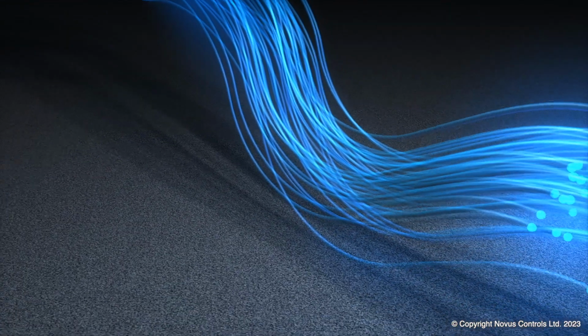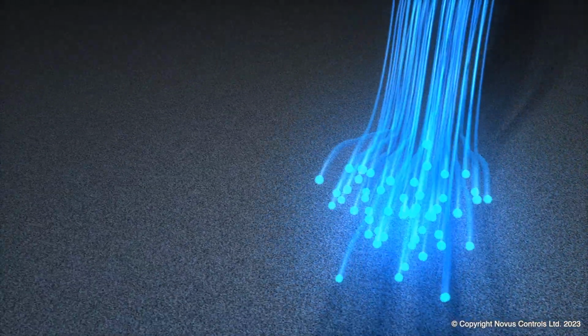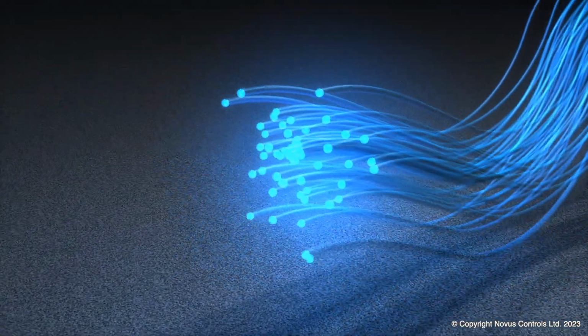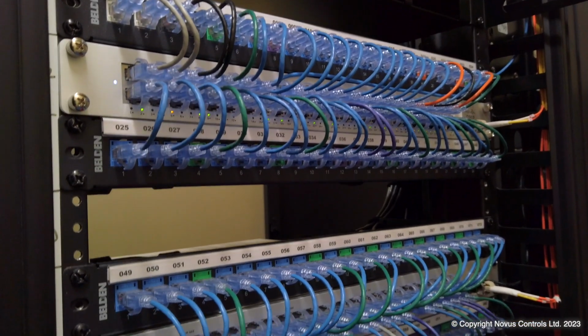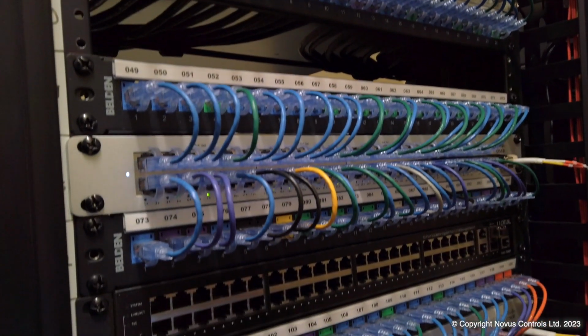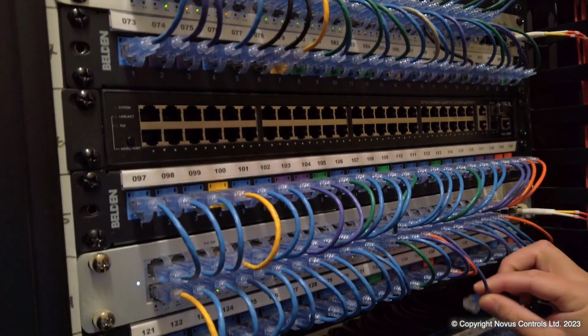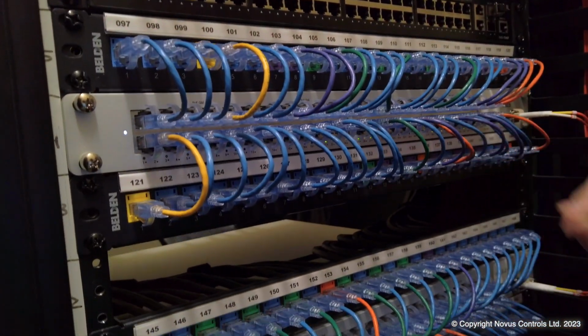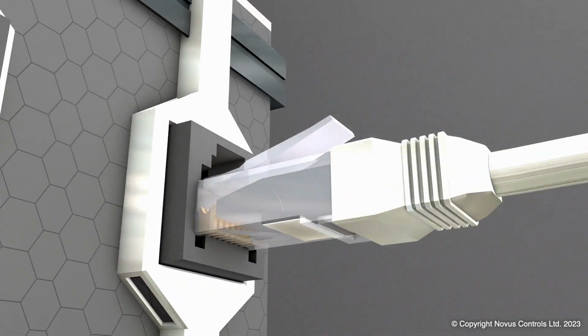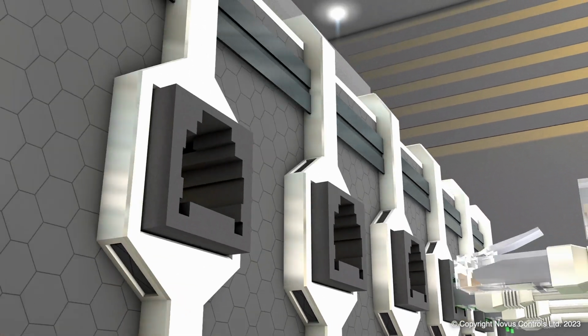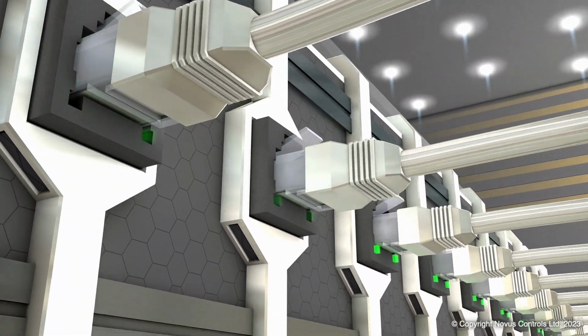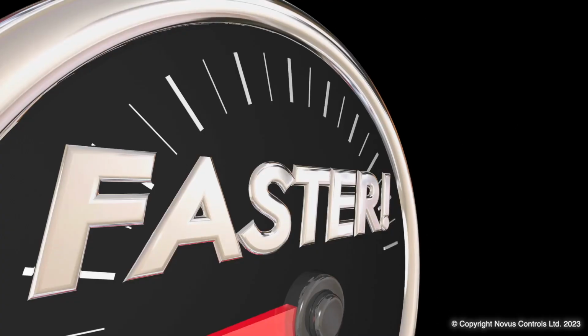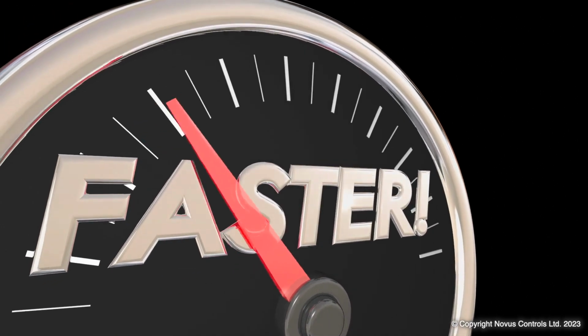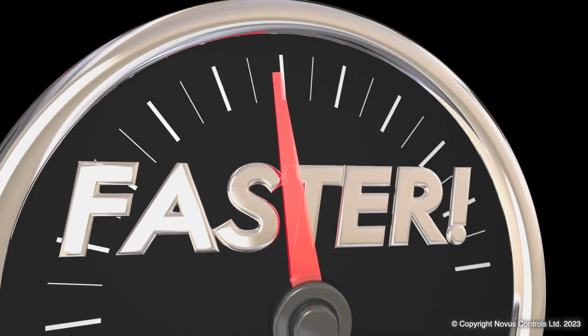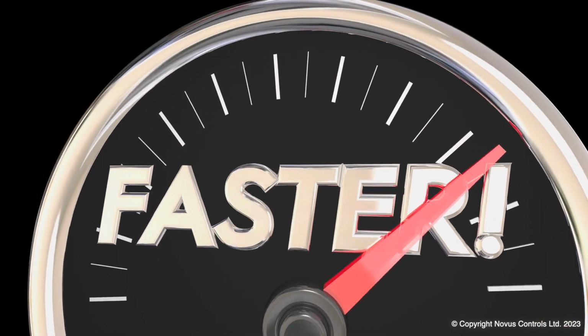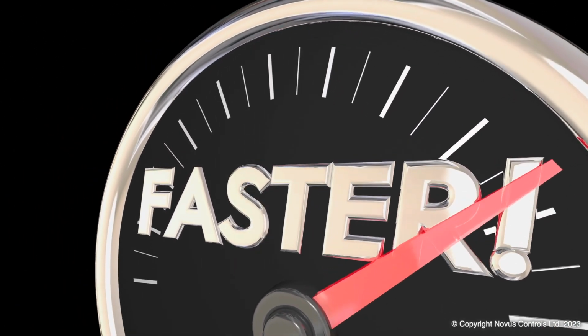It is worth noting that fast data transmission systems will be more likely to use fiber optic rather than copper cabling. For this reason, the switch from Cat 6 and Cat 6a to the newer standards has been slow, as the Cat 6 standard already supports very high transmission speeds. For building automation applications, we often find that our hardware operates using 100 base TX, which can be supported on the old Cat 5 standard. However, it is always sensible to future-proof systems where possible, and so Cat 6 is often specified or adopted as the minimum standard for building automation communications systems.